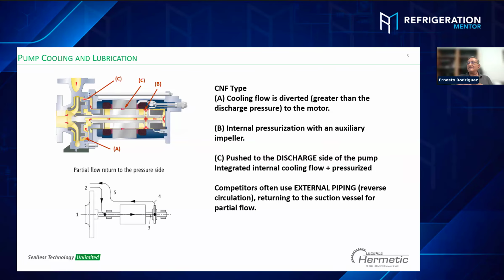Okay, in our pumps, basically we have two types of pumps, single impeller and multi-impeller. For the single impeller, I want to explain how the fluid runs inside the pump. Basically, we have the suction, and the refrigerant runs into the pump through a hollow shaft and goes directly to the impeller. This impeller is going to increase the differential pressure approximately 10 psi. This means the fluid is going to recirculate inside the pump, lubricating and cooling the pump internally. We have this diagram showing the most basic way to operate.